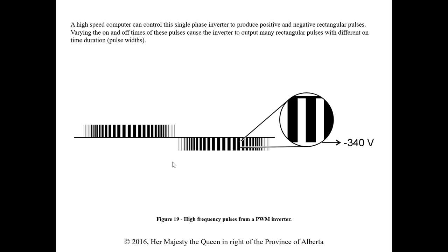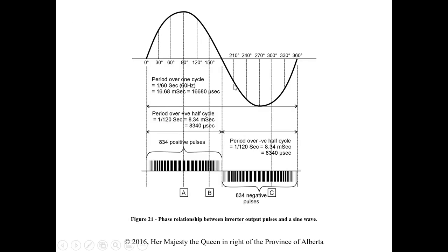By controlling how long those pulses are on, we control the average output voltage. If the pulse is on longer, we see that 340 V for longer, giving a higher average; shorter on-time gives less average voltage. A high-speed computer controls this single-phase inverter to produce positive and negative rectangular pulses with varying on and off times, causing the inverter to output many pulses with different average voltages — effectively mimicking the instantaneous values of a sine wave.